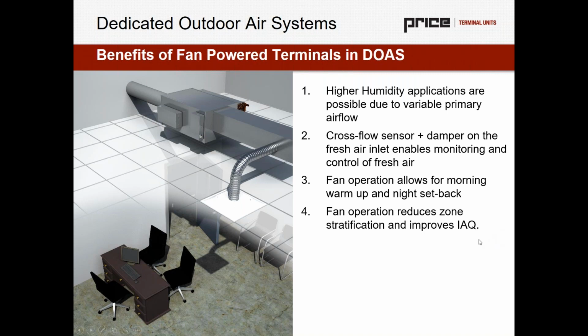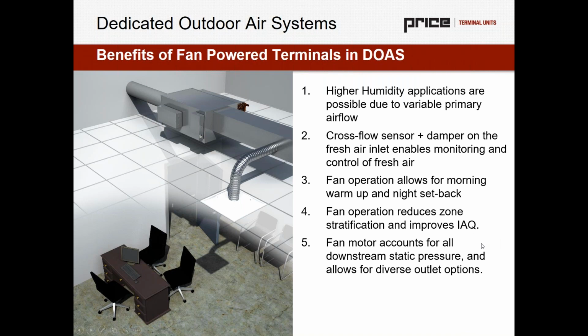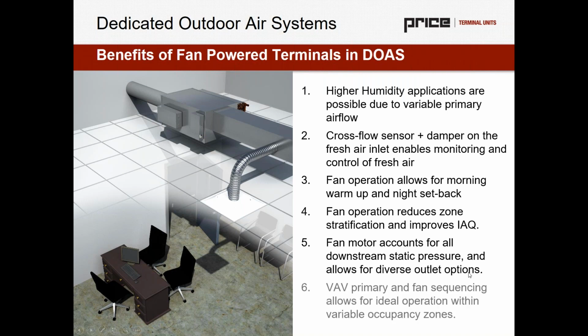The provision of the fan reduces zone stratification and improves indoor air quality. So we can provide a higher volume of air than maybe we could with a chilled beam system, with that fan still operating below 0.12 watts per CFM in deadband, which is going to allow for significant mixing within the zone, less stratification, and as it continues to induce air in and mix it back to the breathing zone, any ventilation air that hasn't been utilized by the occupants can move back into the breathing zone, which is a benefit. That fan motor is going to allow for diverse outlet options because it provides a lot of downstream static pressure flexibility. So long duct runs, multiple air outlets, maybe even mounting the unit overhead outside the occupied space.